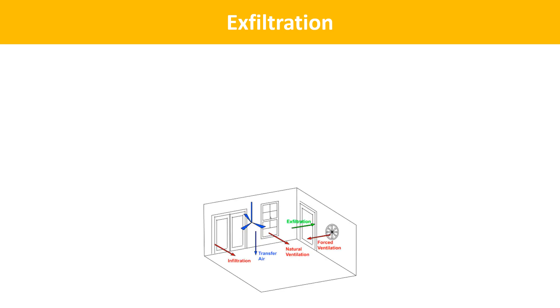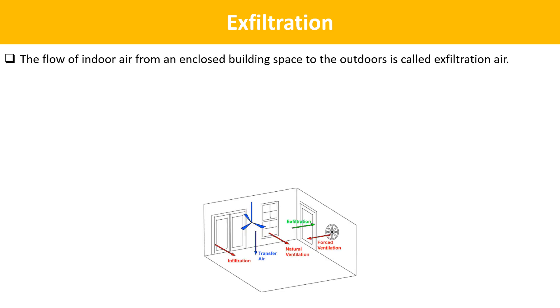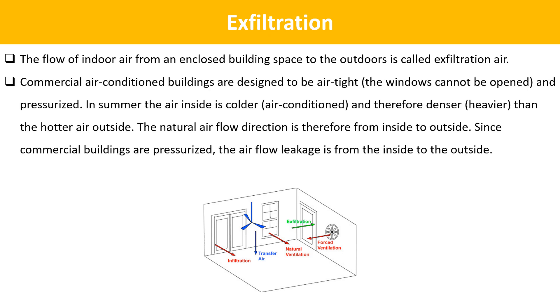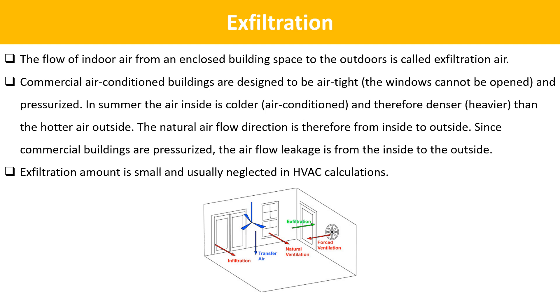The next term is Exfiltration. The flow of indoor air from an enclosed building space to the outdoors is called exfiltration air. Commercial air-conditioned buildings are designed to be airtight — the windows cannot be opened — and pressurized. In summer, the air inside is colder, air-conditioned, and therefore denser and heavier than the hotter air outside, so the natural airflow direction is from inside to outside. Since commercial buildings are pressurized, air leakage is from the inside to the outside. Exfiltration amount is small and usually neglected in HVAC calculations.